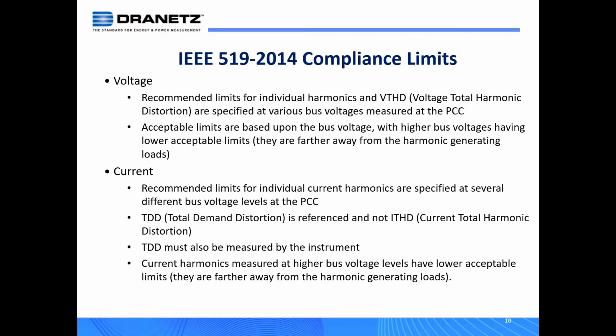Continuing on, there are also current recommended practices, and the recommended limits for individual current harmonics are also specified at the different voltage levels. So 519/2014 asks us to monitor the voltage and the current, and each has compliance limits based upon the distribution voltage that we're monitoring.